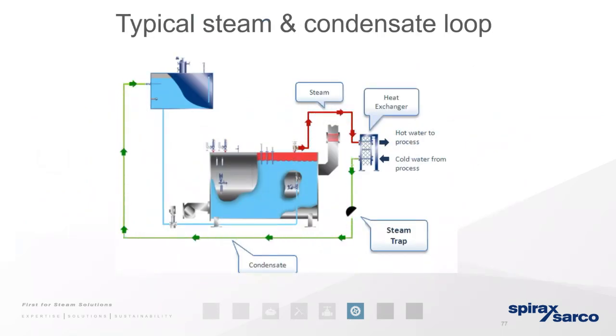So we call it a loop. The reason why we call it a steam loop is because, as you can see, steam comes out of the boiler, enters your process. In this particular case, it's a heat exchanger, then via traps and condensate lines, then returns back to your feed tank, and the process begins again.